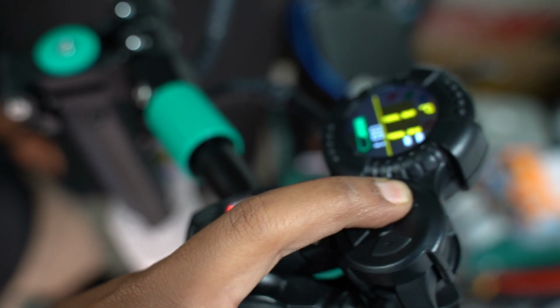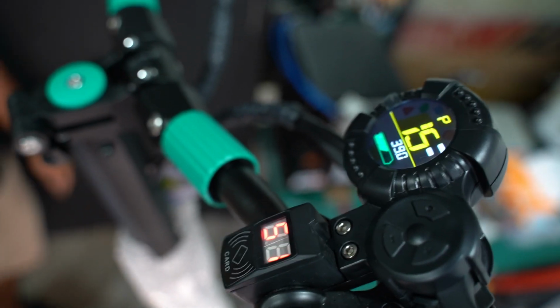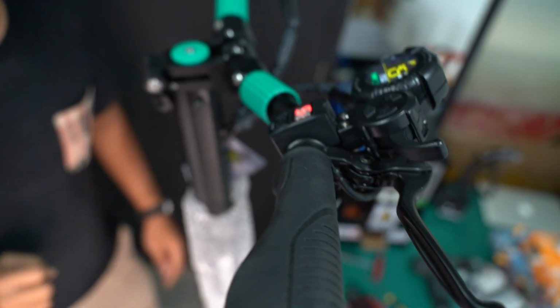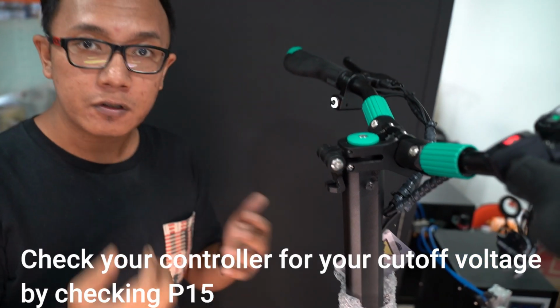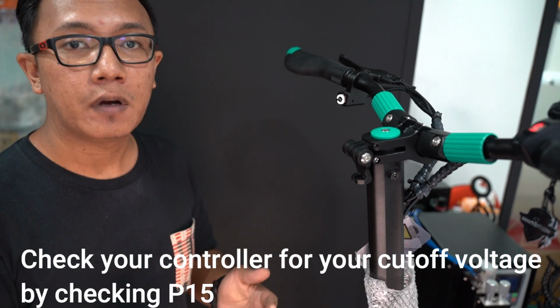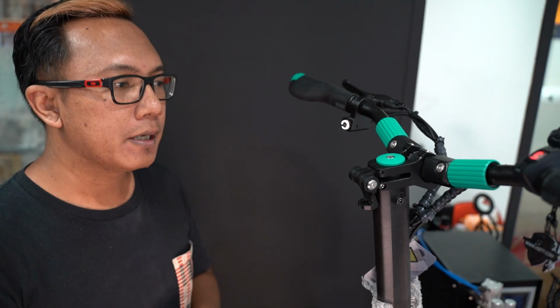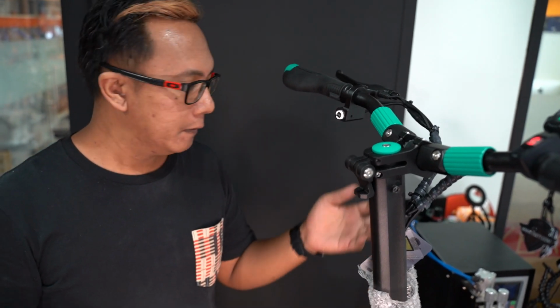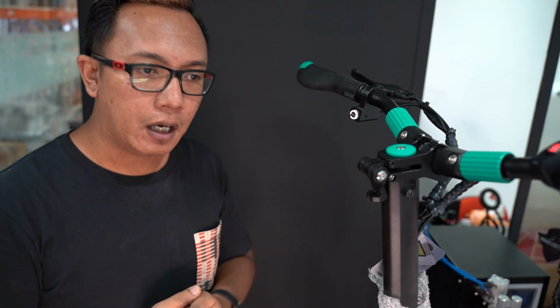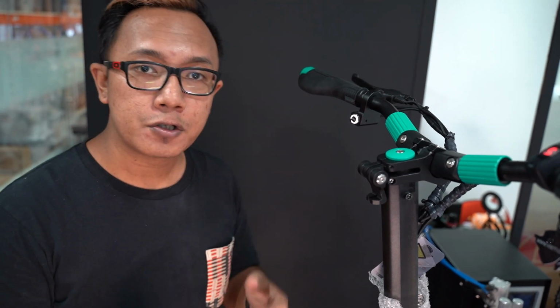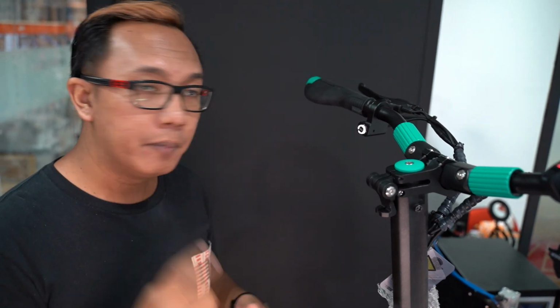So make sure P number 3 is in accordance with your current battery's voltage, and then we'll jog up to P15. A little thing to note is that this is the battery's cutoff value. Different scooters and different controllers have different minimum cutoff values - say if you have a 48 volt, best is to follow your controller's cutoff value. I'll bring one controller to show.